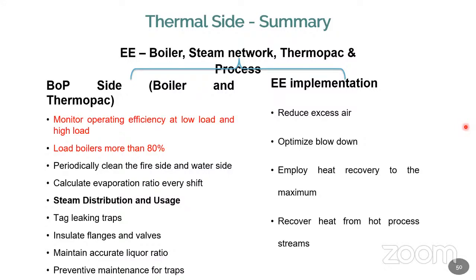Then what are the energy conservation measures you can take from the boiler side and the Thermopac? You have to reduce the excess air by optimizing the FD fan operation. Regularly, you have to blow down, either by shift, by manual or by automatic. You have to measure the TDS level and water quality, then do the blow down. That will also have a good effect on the efficiency of the system.